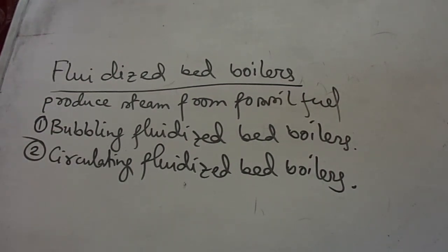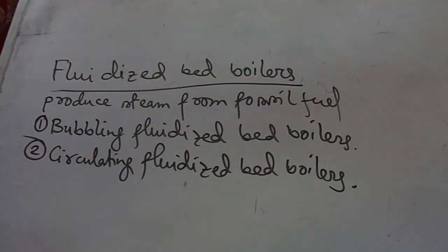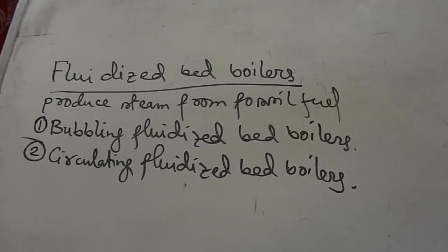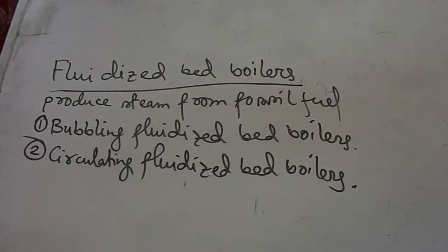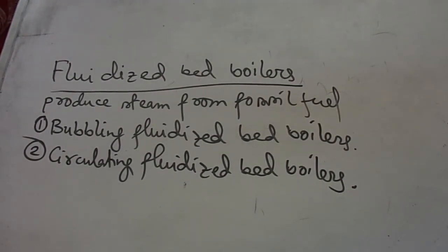In BFB, the bubbling fluidized bed boiler, crushed coal is injected into a fluidized bed of limestone just above an air distribution grid at the bottom of the bed. The air flows upward through the grid from the air plenum into the bed, where combustion of coal occurs.